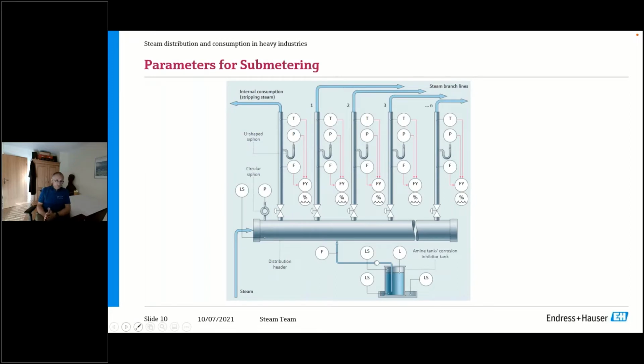So what are typical parameters in submetering? Typically we recommend that you first of all have level inside your main distribution header in order to make sure it does not drown, because this is very important. Otherwise you will have wet steam ending up in your system, and you will want to measure the steam flow to the various points of end use. And you will want to measure the consumption of your corrosion inhibitor. You may or may not inject that at this very point. There are various points in the system where this is typically being injected, depending on the different kinds of chemicals there are about.